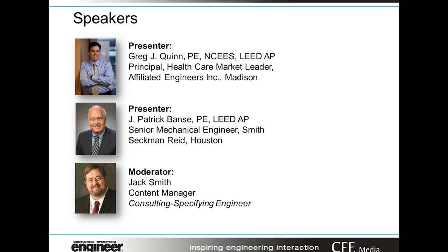Pat, your first question: what differential pressure sensors are most accurate and reliable to ensure that room pressurization is correctly monitored? That's an excellent and frequent question. Sensors measuring between a corridor and an isolation patient room or an operating room need to be positioned correctly and need sufficient sensitivity — reading to at least a hundredth or a thousandth of an inch of water column. More than anything, it's placement and the controls of the air systems that will make those measurements work best.